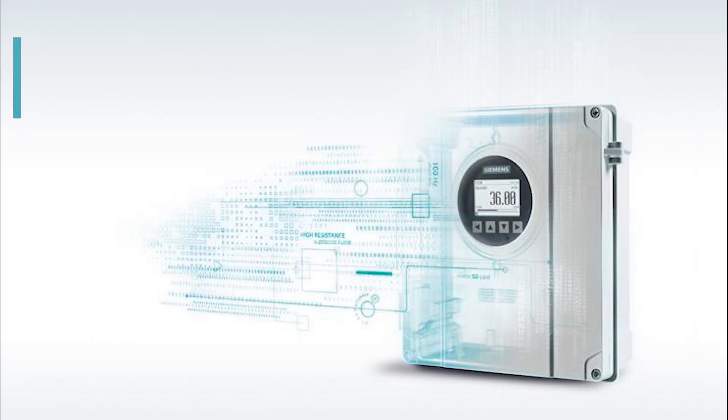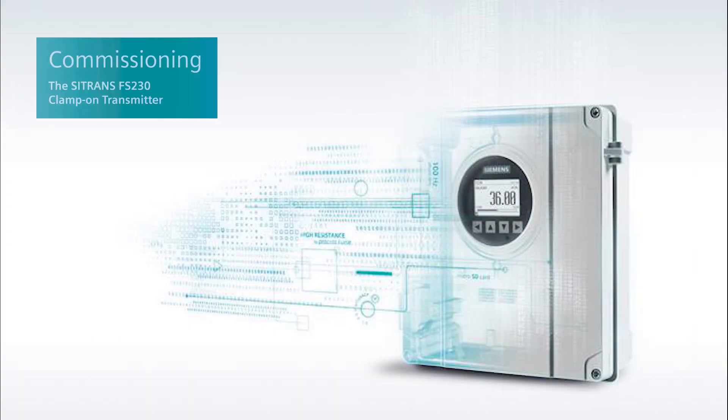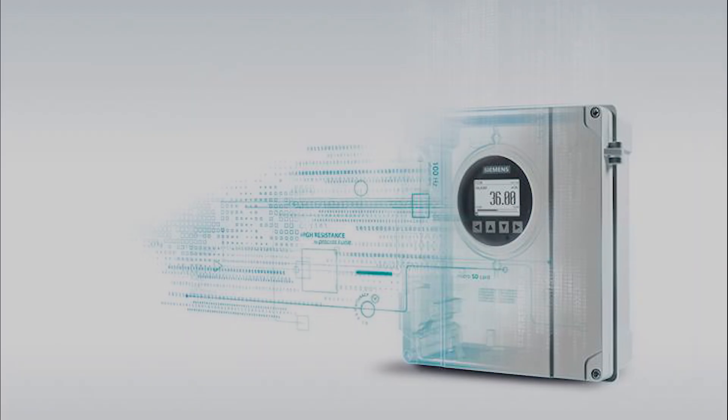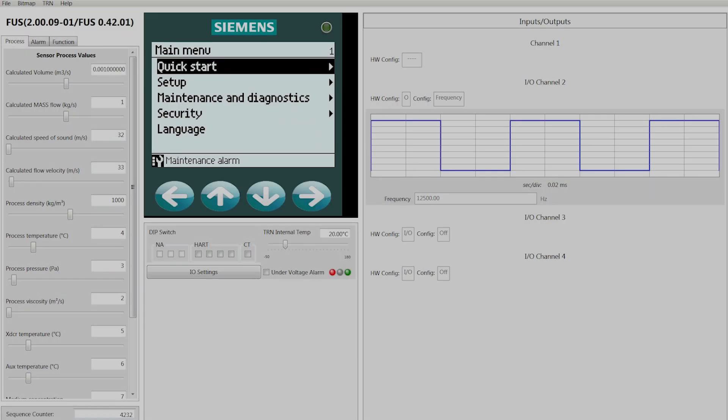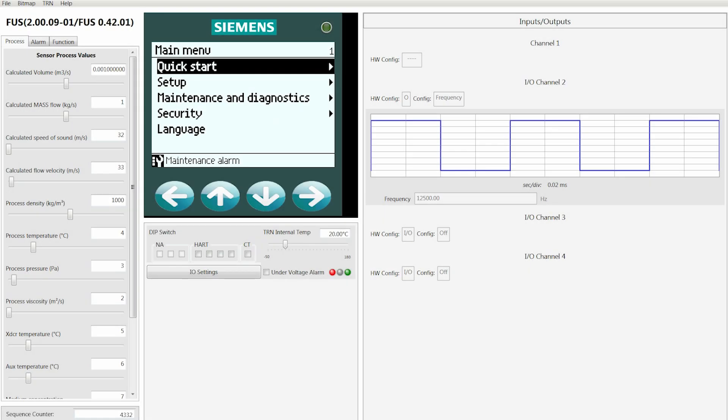This is a series of three videos that will walk you through the commissioning of the Siemens FS 230 clamp-on ultrasonic transmitter. Once you land on the main menu screen, select your language. This can be done by using the down arrow to Language and then pressing the right arrow key.